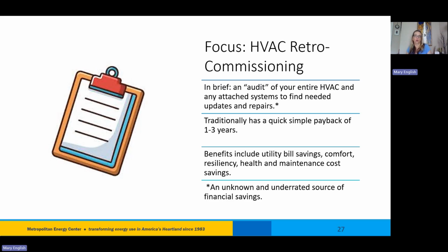You can expect maintenance on your equipment to also cost less. One of the board members at Metropolitan Energy Center used to work in telecommunications and built 175 brand new LEED certified retail outlet stores. That process required a commissioning after the install of the HVAC equipment, and they realized $1,500 a year savings per retail outlet in maintenance costs alone. So that adds up, and anything related to the HVAC system relates to comfort and health. It's highly recommended this get done in your building if it hasn't been done before, and you'll reap the rewards in return on investment, comfort, and durability.